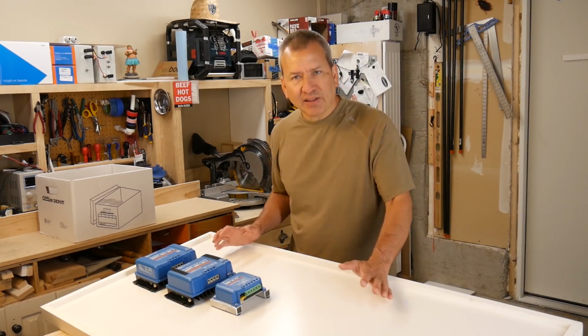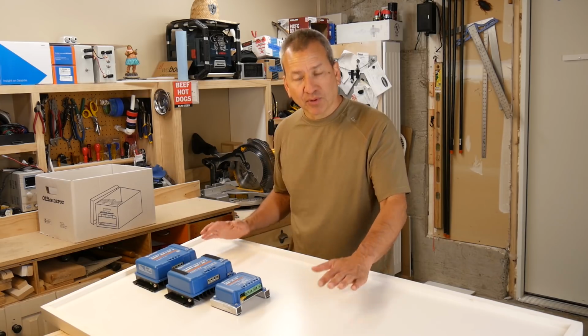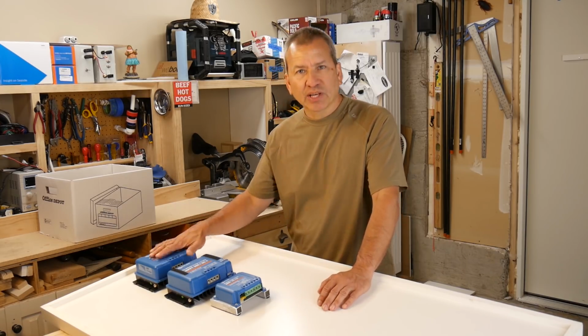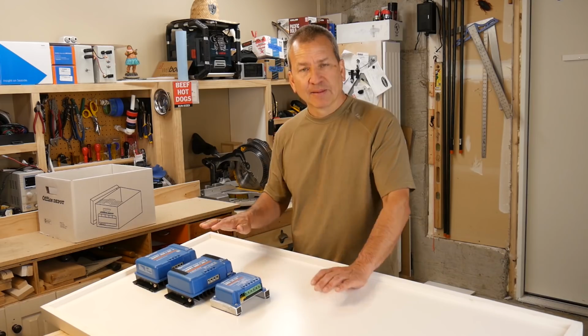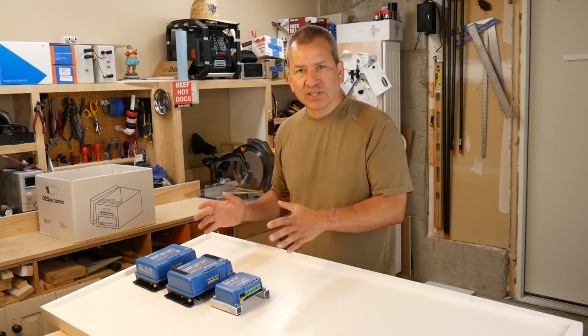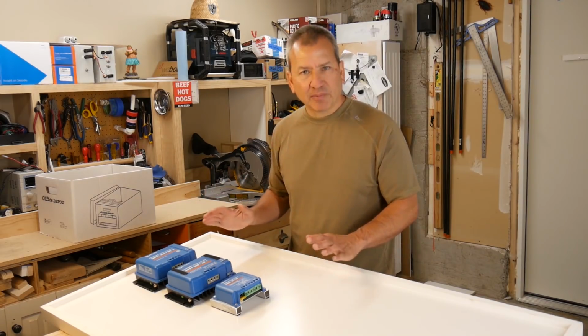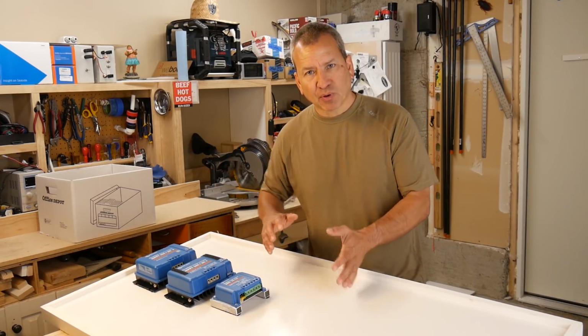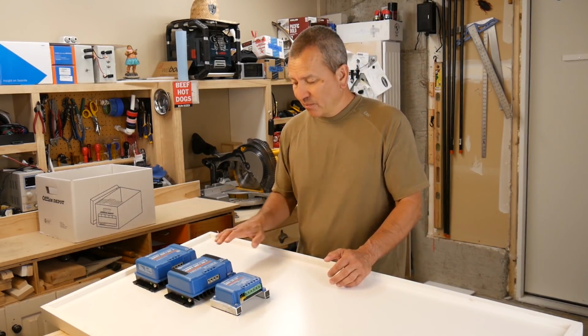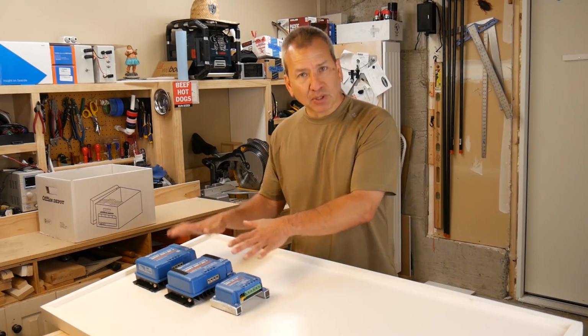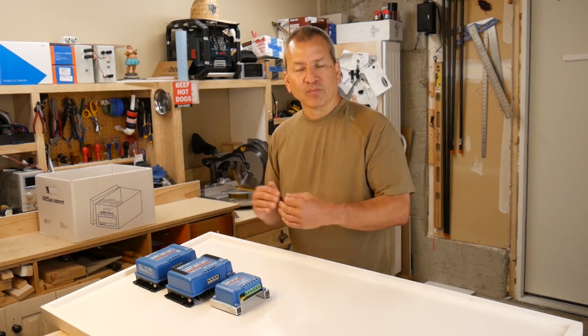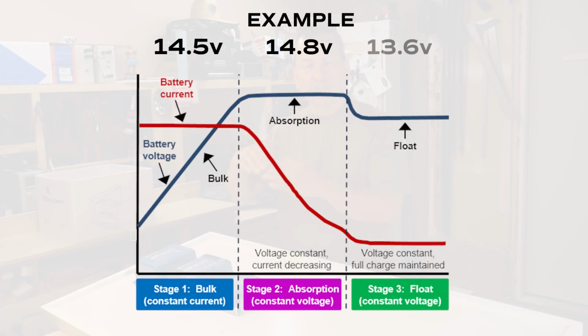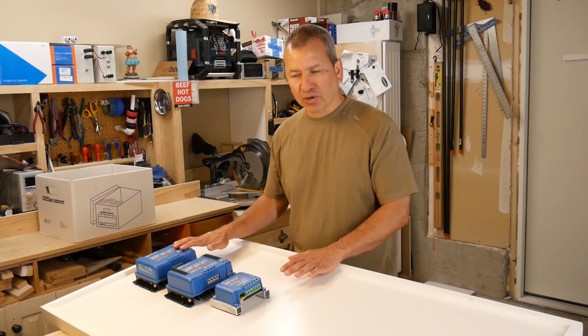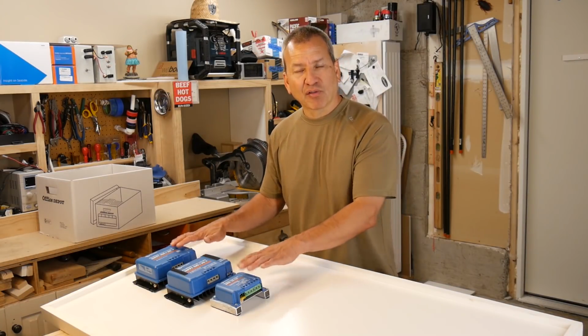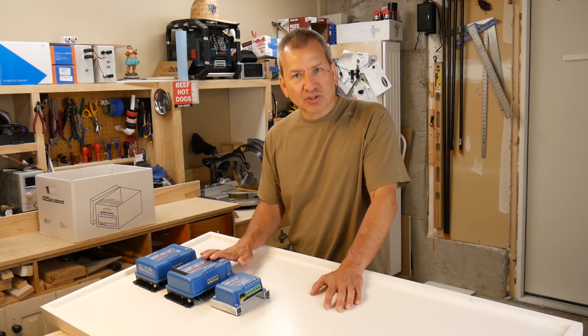The second thing we need to do is make sure all three charge controllers are programmed the same way, so they share the same charging profile for my battery. These multi-stage chargers charge up to a certain voltage and then switch to a different phase of the charging cycle, and we want that switch to happen at the same time for all three controllers.